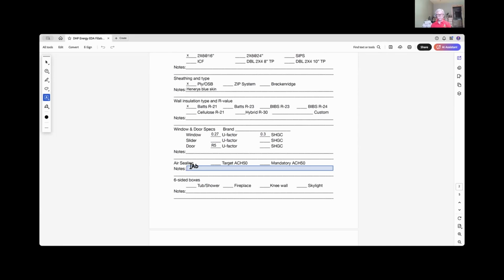I'm so glad you brought that up because I do a lot of commercial testing as well, and that's all based on enclosure. Oregon is very progressive - we follow ASHRAE 2022 standards, and it's 0.35 ACH on all commercial buildings. Anything under 10,000 square feet mandatorily has a blower door test. Anything over 10,000 square feet is either a blower door test, or a plan review pre-submit with site inspections throughout the build and a report.